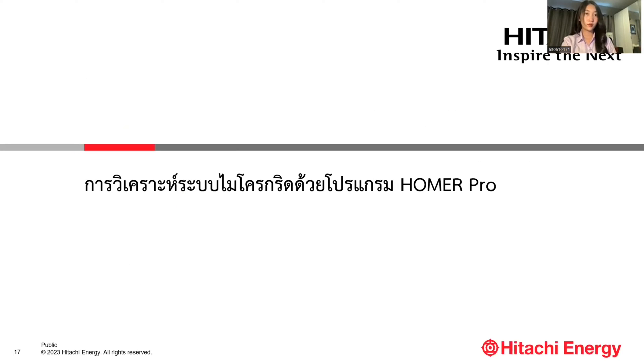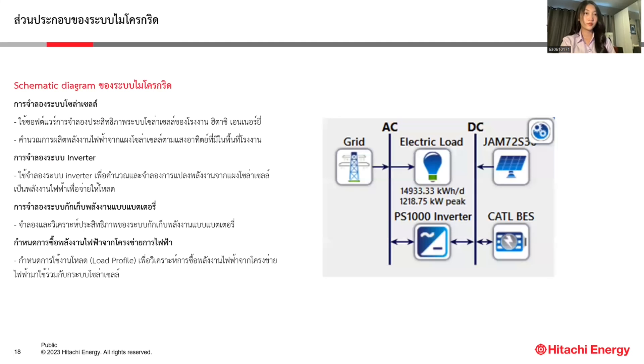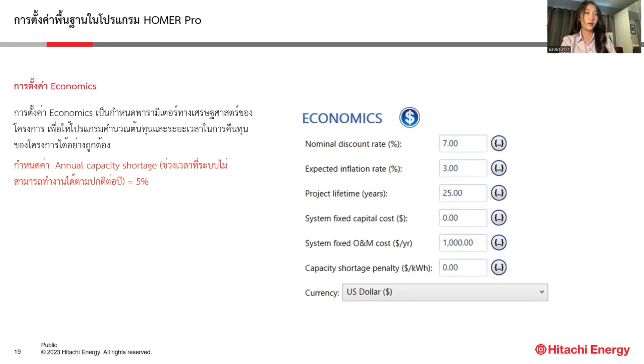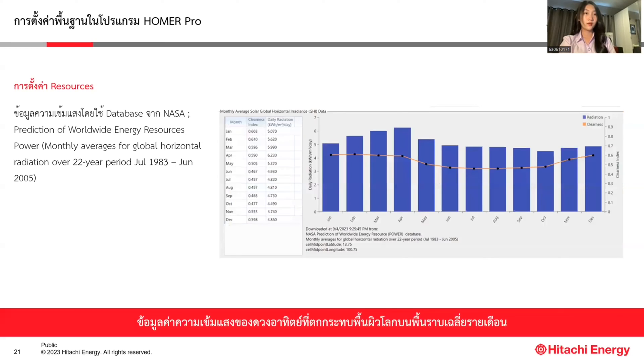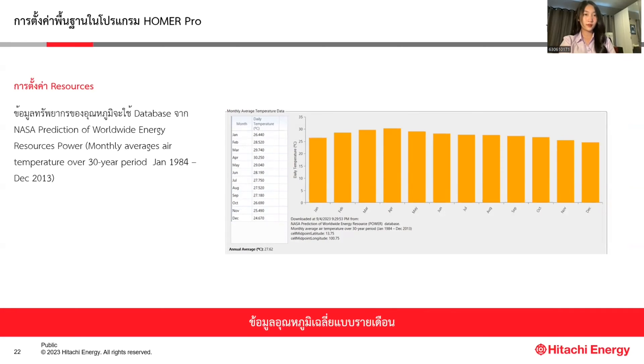The analysis continues with the microgrid system analysis using HOMER Pro. After configuring the data, the program generates a schematic diagram as shown. Economic parameters are set to calculate the project's cost and payback period accurately, including a discount rate of 7%, an inflation rate of 3%, and a project duration of 25 years. Data for irradiance and temperature are imported from project-specific locations, with both sourced from NASA.